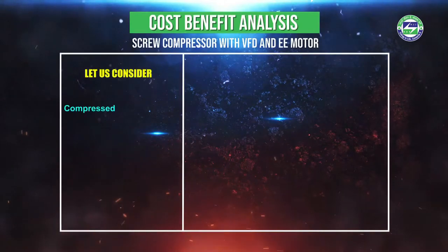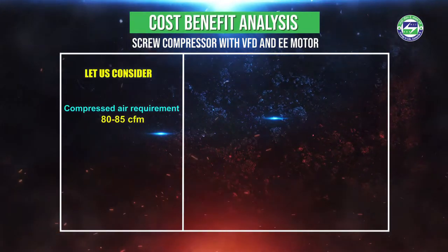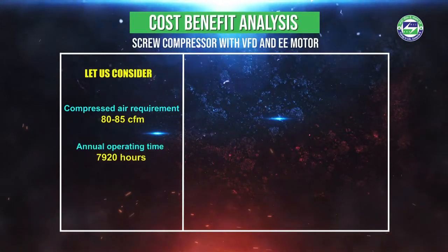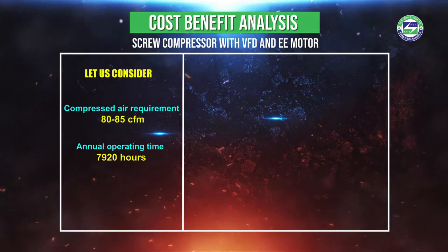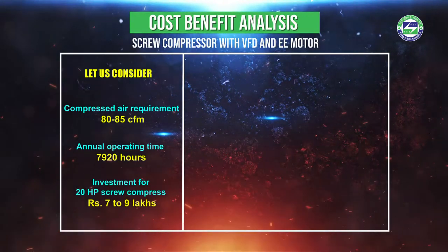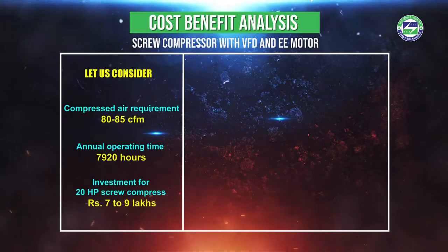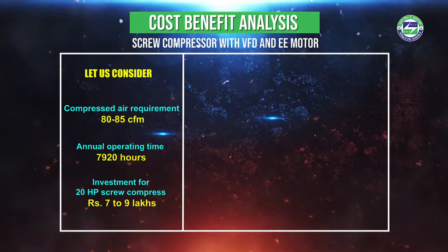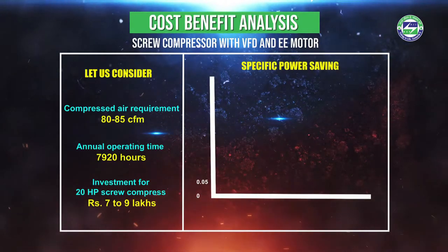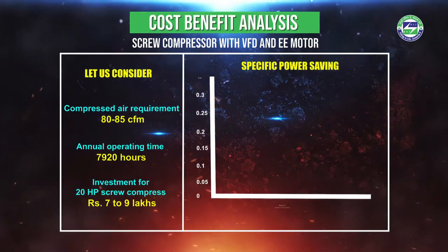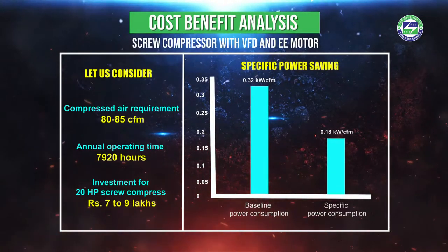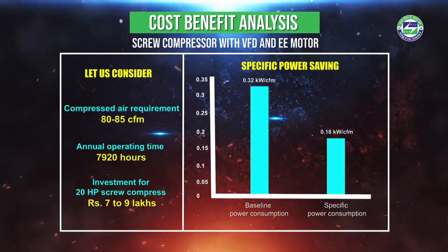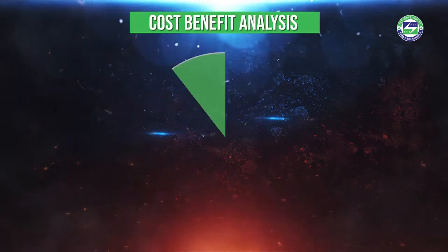To understand the cost-benefit analysis, consider an 80 to 85 CFM compressed air requirement with an annual operation of 7,920 hours. A 20 horsepower screw compressor is suitable for this requirement, which will require an investment in the range of rupees seven to nine lakhs. The installation will lead to a specific power consumption of around 0.18 kilowatt per CFM, from the baseline level of around 0.32 kilowatt per CFM.